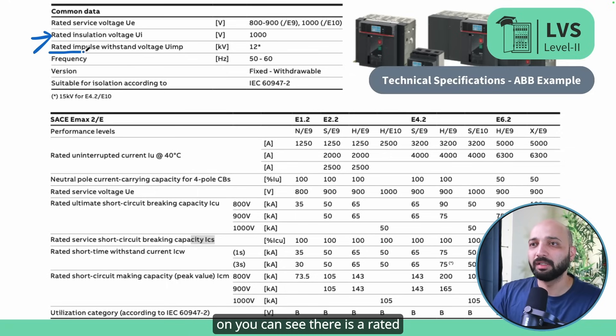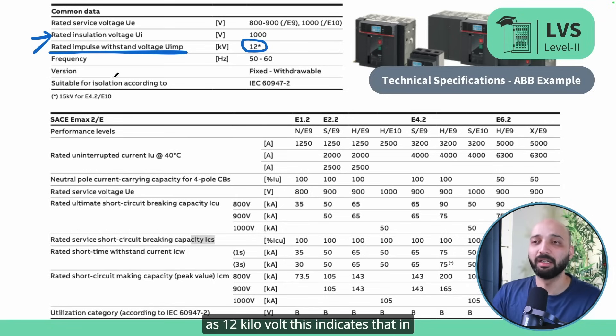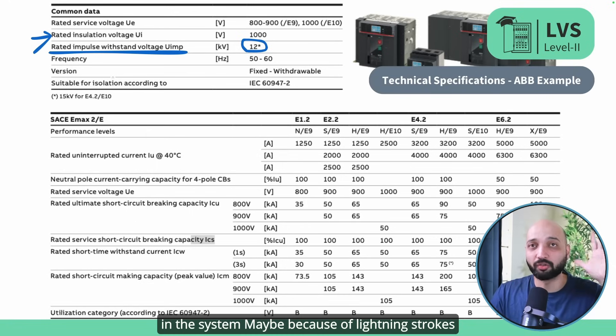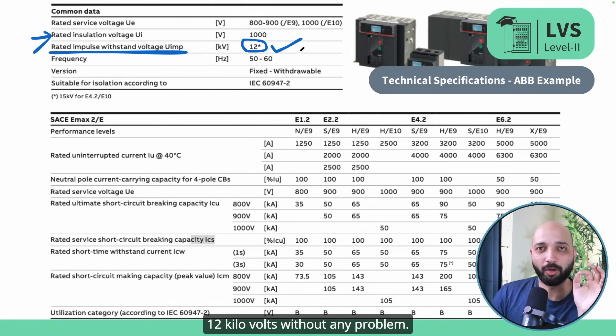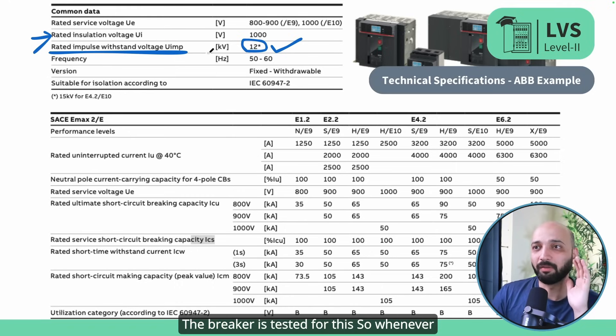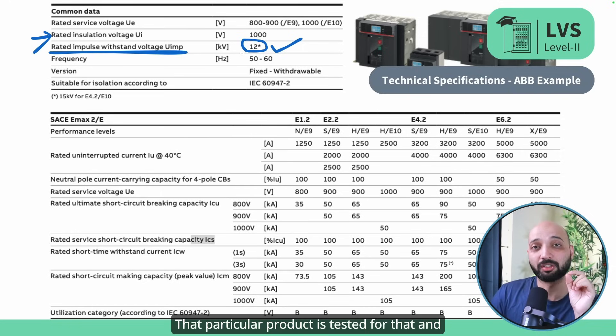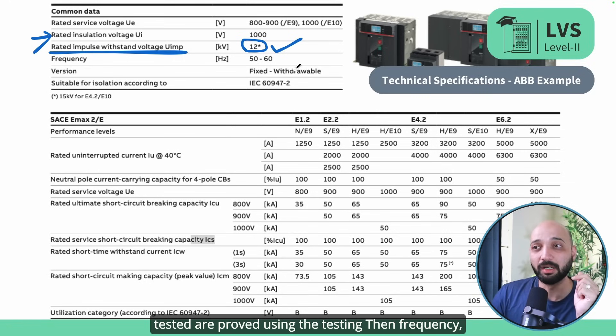Next is the rated impulse withstand voltage, Uimp, mentioned as 12 kilovolts. This indicates that if an impulse voltage occurs in the system — maybe because of lightning strokes or load shedding — the breaker is capable of withstanding 12 kilovolts without any problem. The breaker is tested for this. Whenever values are mentioned in a datasheet or technical specification, that means the product has been tested and proven for those values.